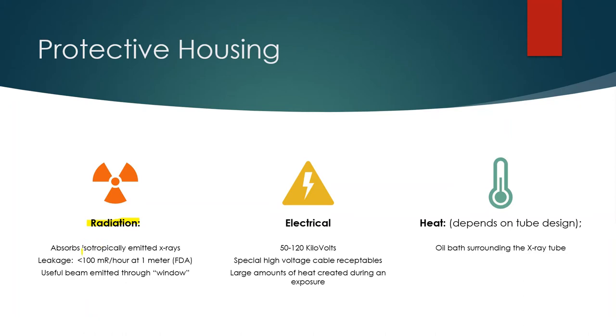The protective housing is there to limit leakage radiation. Radiation travels isotropically, meaning it travels in all directions away from the source — similar to dropping a pebble into a pond and watching ripples move outward. The electromagnetic energy, even though it travels at light speed, travels in wave form away from the source. The goal of the protective housing is to limit leakage radiation to less than 100 millirad per hour at one meter from the source. This is an FDA regulation, and the useful beam is emitted through the window.